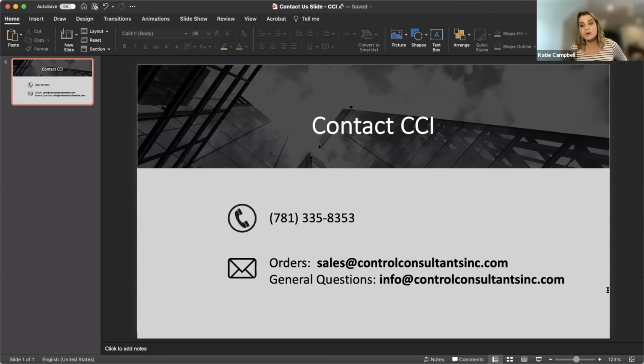The next question, from Ron, came in prior to the webinar: can this system be integrated into a Niagara system such as a Jace 8000, and if so, what is the COM protocol? Good question. Quick answer is yes, it can be integrated. The Prolon system as a whole uses the Modbus RTU protocol. I believe the Jace 8000 already comes with a Modbus port—Jim can give more details.